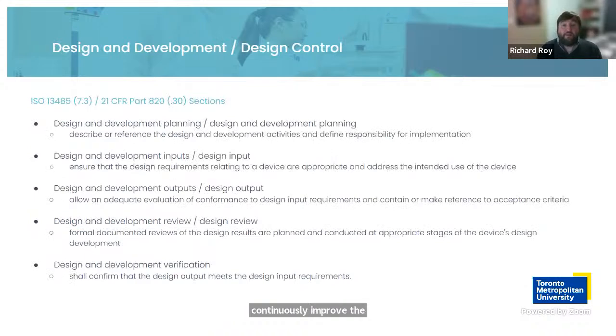So one area I did want to specifically talk about, as you look at your journey into this medical technology field and developing medical products, is the design and development part of that quality system I was just mentioning. I'll go over briefly some of the main sections of this, and the importance of this is because of the process involved in design control. On the left is the ISO 7.3 standard, but then there's also the equivalent in the Part 820 standard, which talks about planning. That's why you see the slash in the middle. They just describe it slightly differently between the regulations.